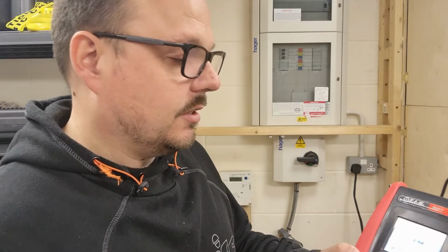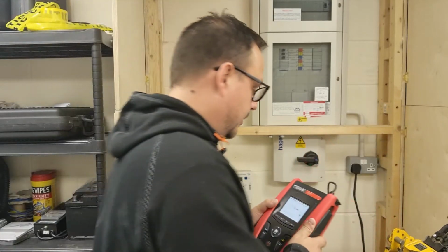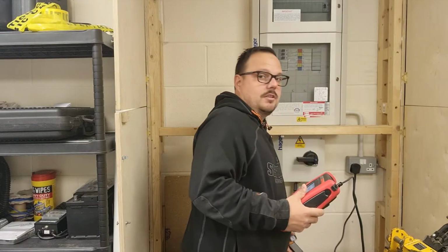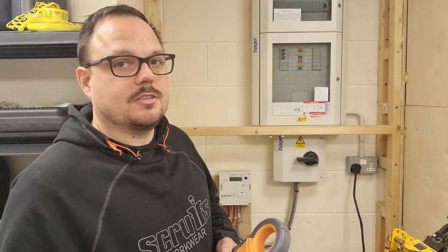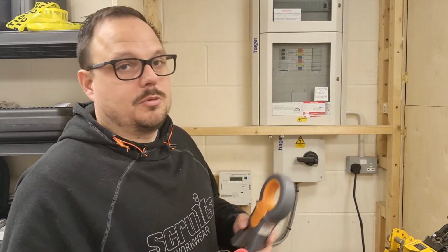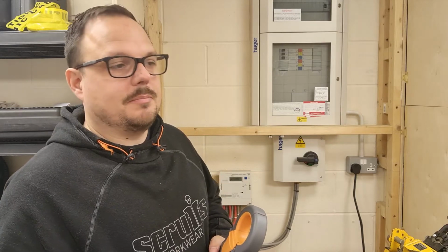So I will keep it onto the scale that we need it for this particular measurement. So we're showing 2 milliamps, but it is adjustable like you have on most of your clamp meters. So if you're going into a domestic property, for example, where you're looking at perhaps changing a consumer unit, so you're just at the quotation stage advising the client of an EICR, you can have a pretty good idea, as we all do when we're first going out to quote, if there's leakage current on the earthing, protective earthing conductors, then you know there's chances are we've got a few issues in there to find.